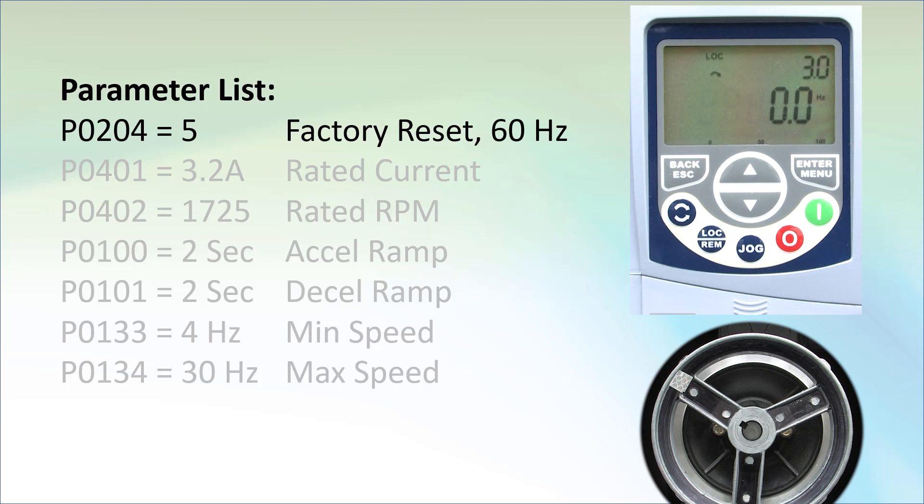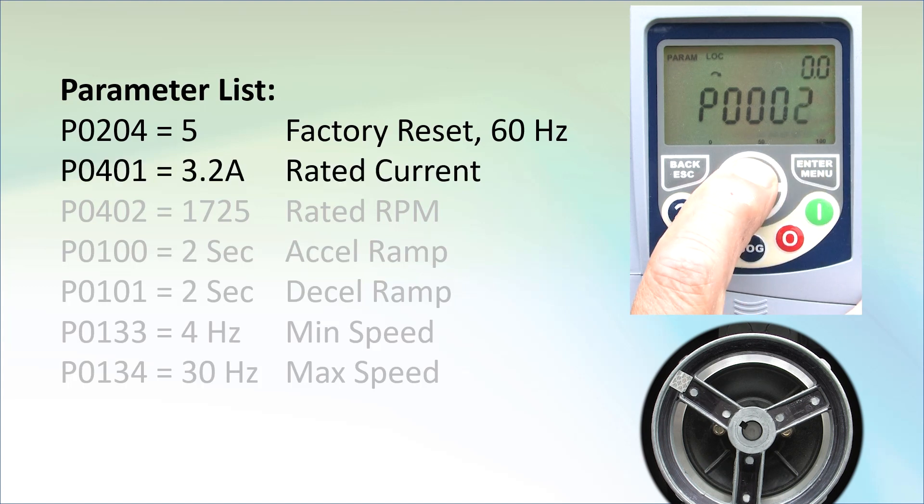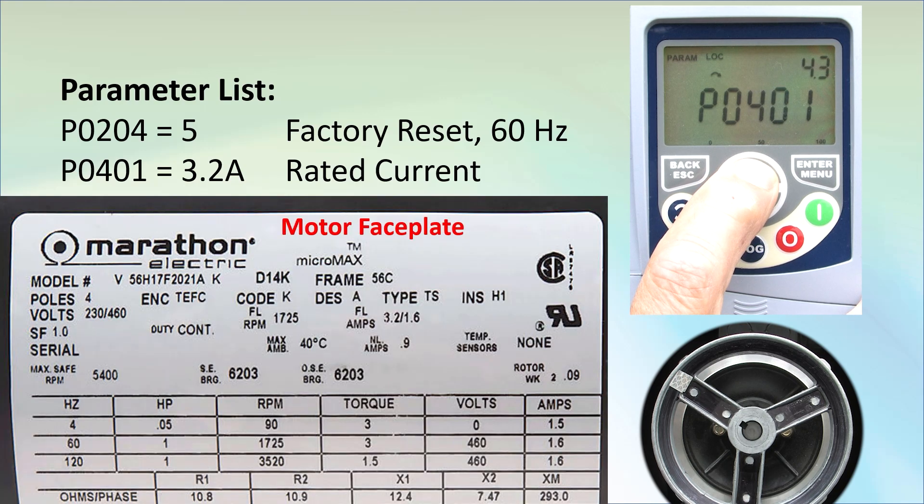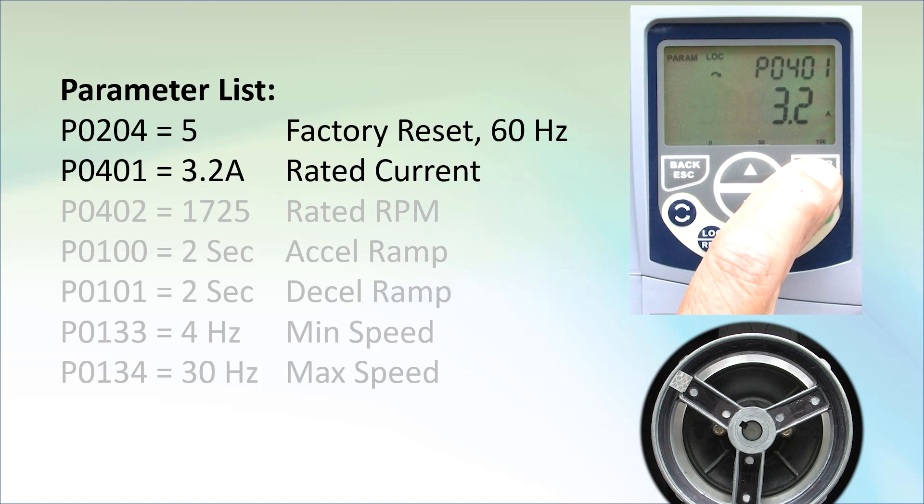Let's configure our motor. Enter to bring up the parameters menu and press enter again to select the parameters group. Scroll to parameter 401 which is the motor's rated current. We see it is currently 4.3 amps. Our motor's faceplate tells us ours is 3.2 amps at 240 volts. So we enter into the parameter, change it to 3.2 and enter to accept.